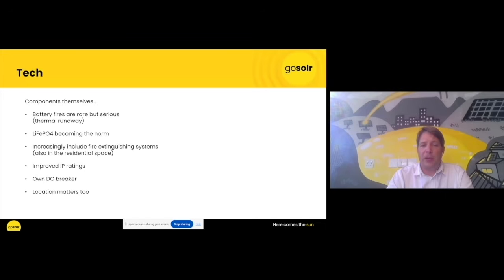We see improved IP ratings. Some of the older batteries are rated IP20, which is not offering much protection against water ingress. The new ones are IP65 or 66 in some instances, which means that you're less at risk of water seeping inside the battery and then either interfering with the BMS and worst case creating some corrosion or short circuit in the battery, which can lead to thermal runaway.